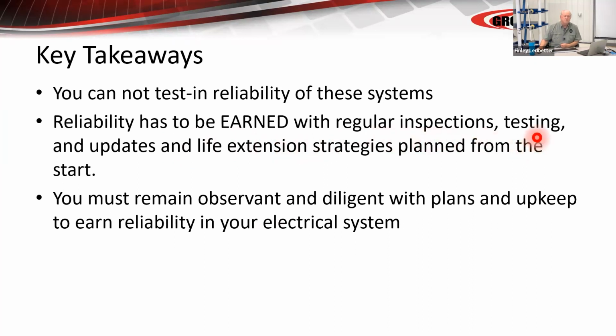And if you look up here, when I said reliability has to be earned with regular inspections, I put inspections before testing for a very good reason. Inspections are far more important than testing, okay? Putting human eyes on it, seeing if it's dirty, seeing if it's clean, listening to it, paying attention to the condition of the equipment, looking underneath the equipment to make sure a lot of the oil and grease hasn't leaked out of it, looking under the equipment to make sure there's not a pile of metal filings underneath it on the cubicle floor, looking at the relaying to make sure there's not a burnt spot on a PT or a CT, and there's not a big PD signature or acoustic signature. All these sorts of things come in inspections.